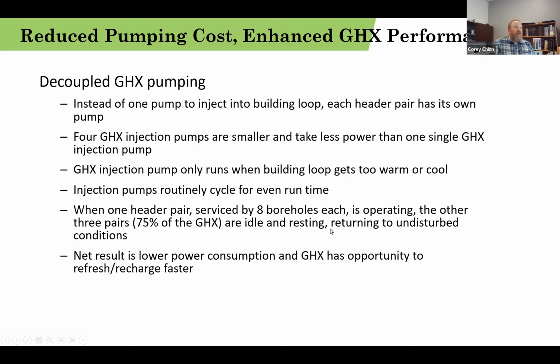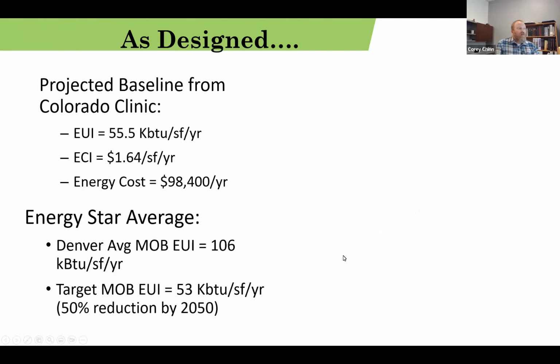So our injection pumps cycle routinely for even runtime. When one header pair is operating, the other three pairs are idle and resting most of the time, and they return to undisturbed soil conditions. So we do believe this had a major contribution to our energy performance here. We're going to take a look at, as designed, projected baseline results. So our baseline would have been 55 and a half kBTU per square foot per year. Our cost index would have been $1.64 per square foot per year from a baseline perspective, for a total energy cost of $98,000 a year.